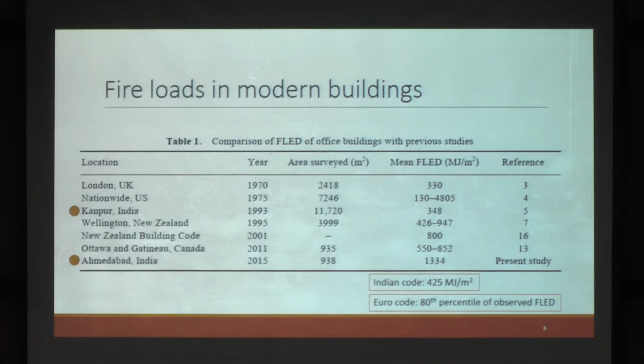So this number from the 20 years ago data is okay, but from the current data perspective, it is actually 1/3 of that. And for a really performance-based design, most of the leading codes suggest that an 80th percentile of the FLED is to be used. So if you assume a normal distribution, a mean will be a 50th percentile. So 80th percentile will be even more than 1300. It will be close to 1900 sort of number. So basically, the designs are severely underestimating the fire load.